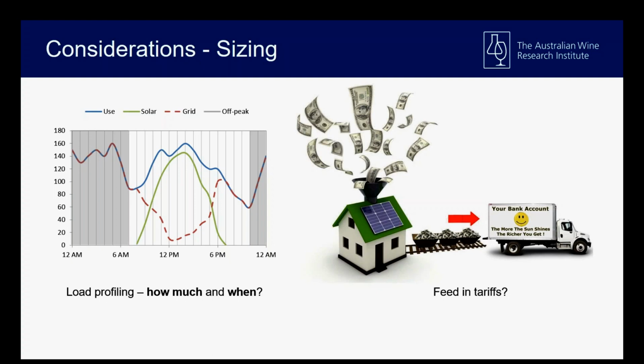This doesn't have to be a risk. If you were in that situation, you'd just have a controller that cuts the connection before you export. But in most situations there's no benefit to an oversized system, it's really just wasted capital, so you need to look at your load profiles and how much energy you can actually use to come up with an appropriately sized system.